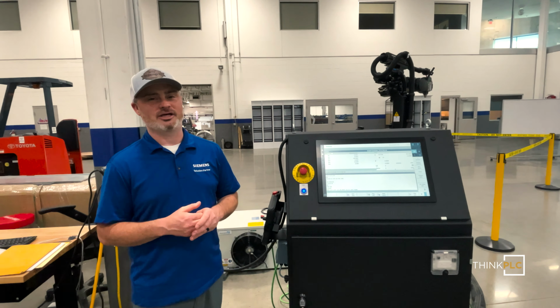From a safety perspective for plant design, we changed things up for UL purposes and arc flash purposes. We wanted the low voltage control to be accessible, and the high voltage control on the backside to be more enclosed, a safeguarded interlock system.